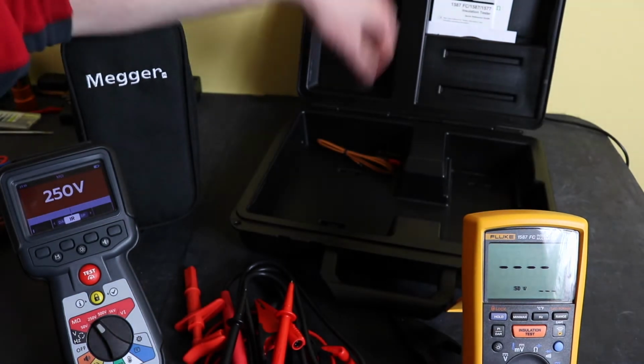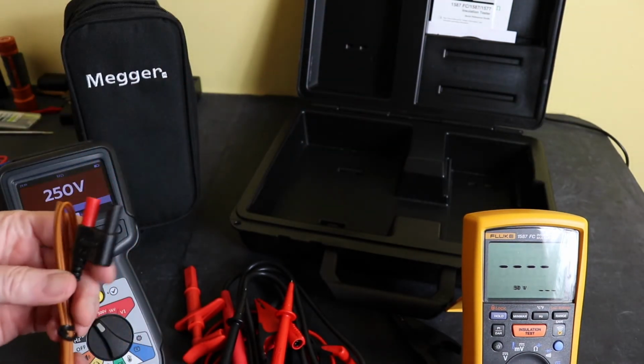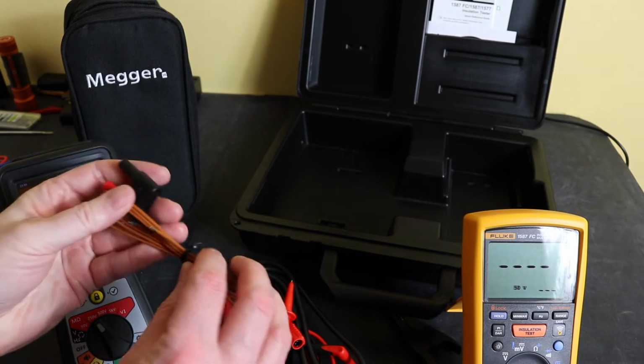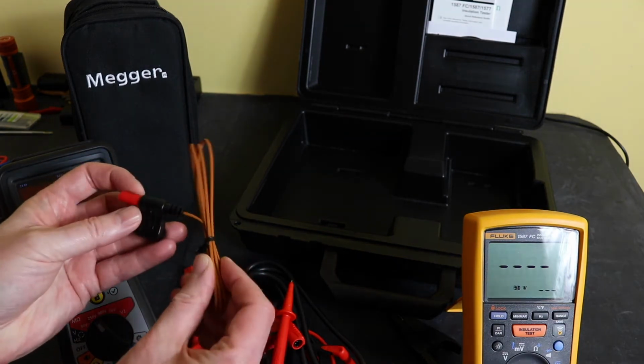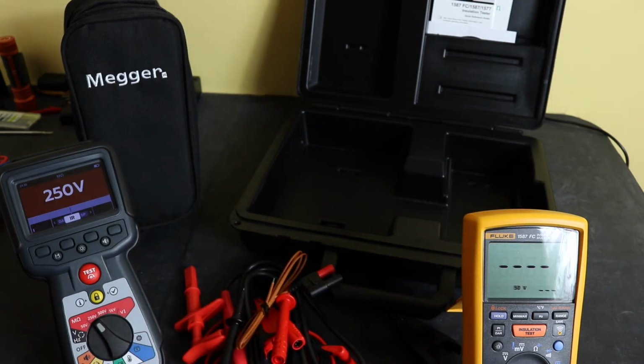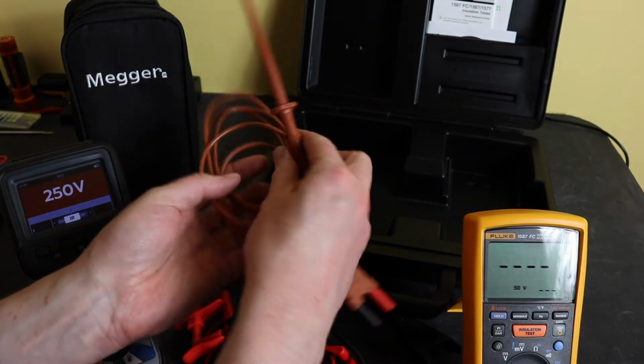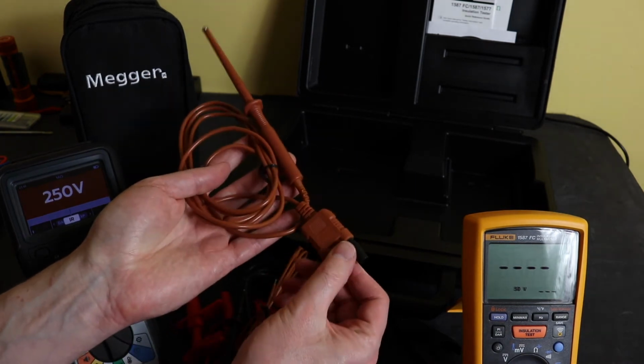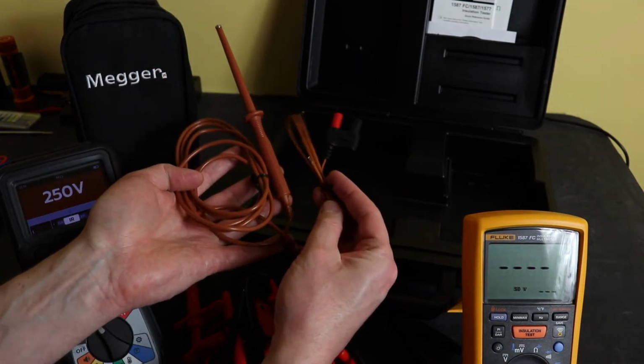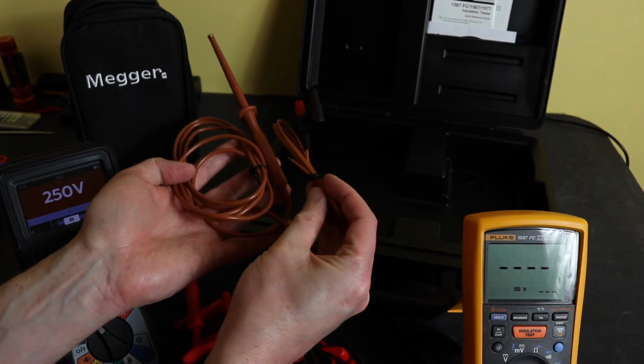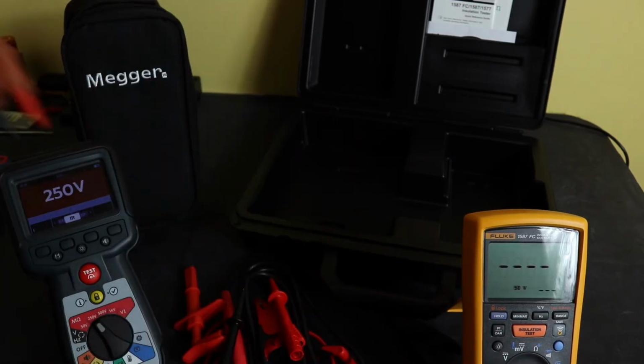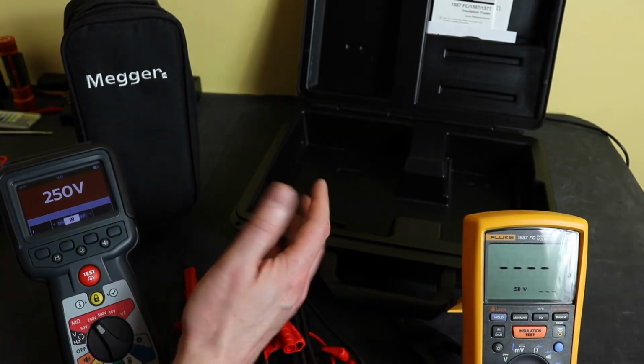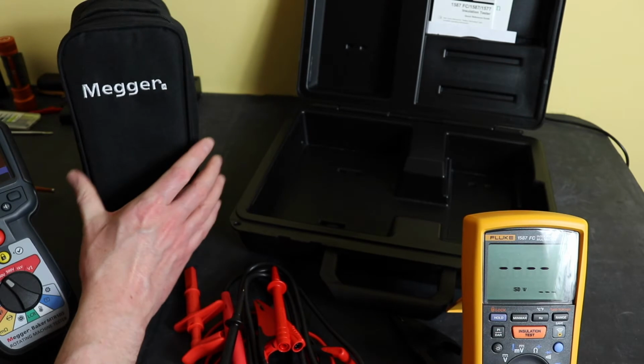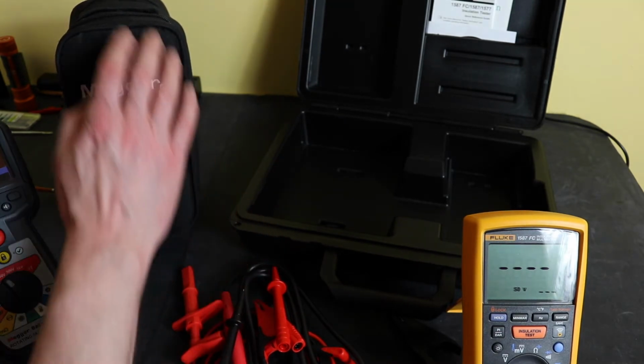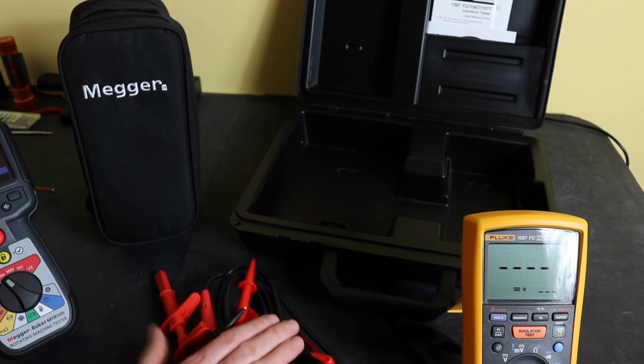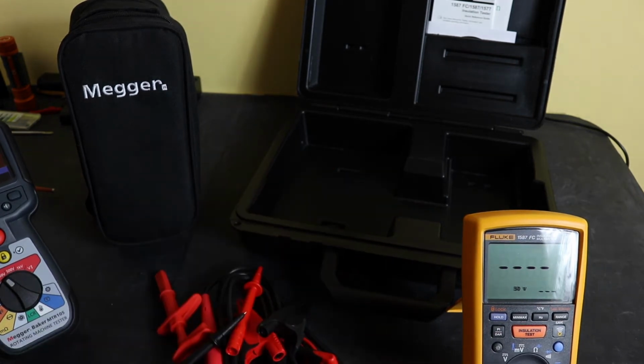The final bit you get with the Fluke is the temperature probe, a standard thermocouple, really. What you get with the Megger in that respect is this T-type probe here. Quite a bit better offering that you get with the Megger for that aspect, really. Okay, and obviously, case-wise, whether you prefer the hard case from the Fluke or the soft case of the Megger, obviously with this, you've got loads of room to put everything in this case.